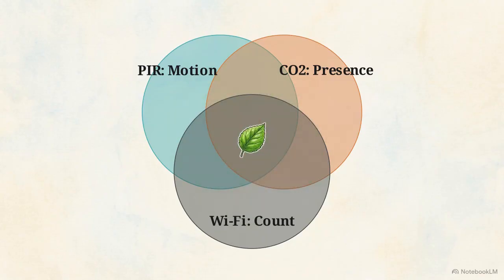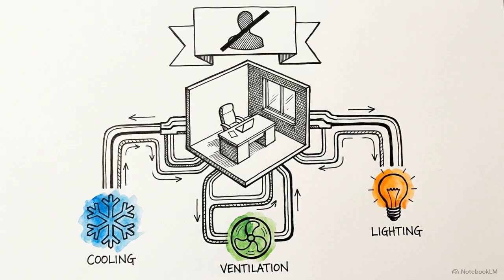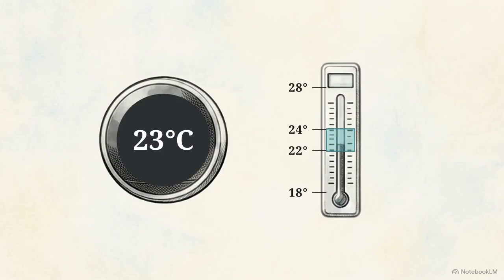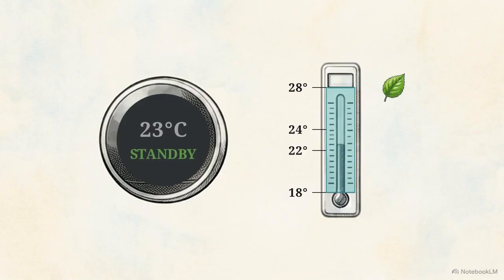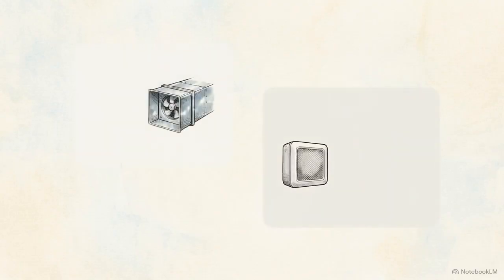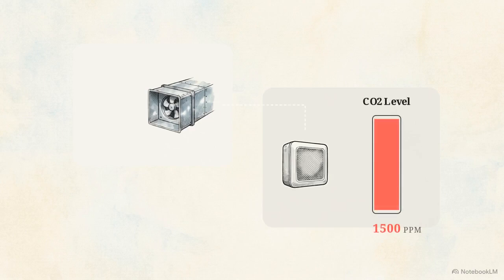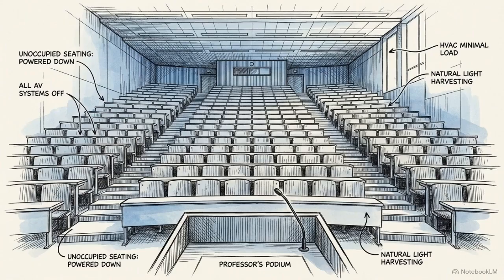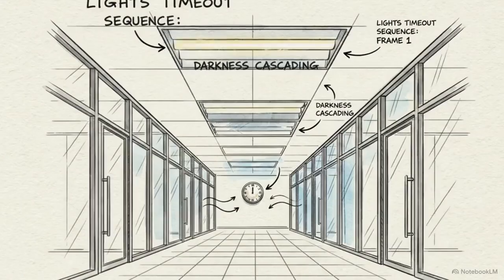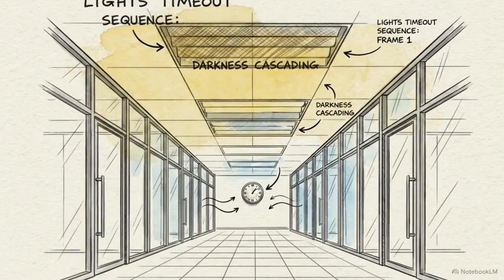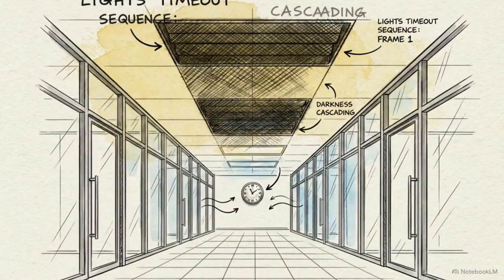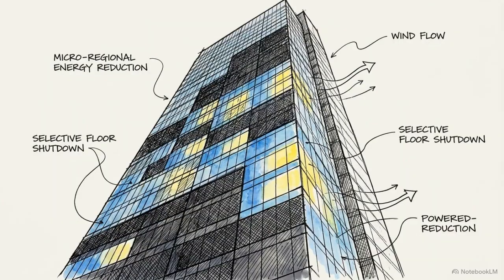Once the BMS confirms a physical space is empty, it executes 3 specific actions to immediately stop wasting energy. First is set point widening. The system relaxes the temperature boundaries so that heating and cooling equipment can safely power down. Second is demand-controlled ventilation. Instead of running fans continuously, the system scales fresh air intake back based on CO2 readings, which is critical for spaces with highly variable head counts, like lecture halls. Finally, lighting follows presence. The system relies on short timeouts to shut off lights completely after a few minutes of detected stillness. These 3 automated responses, executed micro-regionally across massive structures, are the invisible mechanisms that ultimately generate that 40% energy reduction.